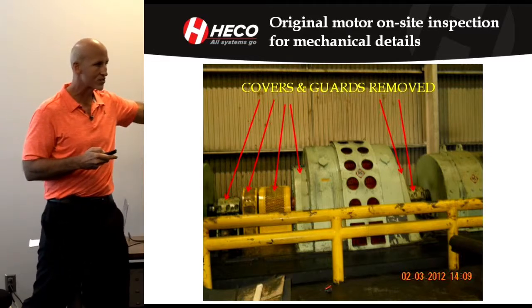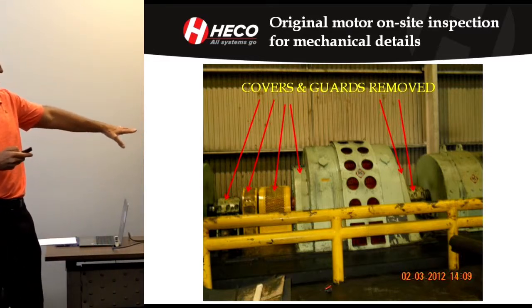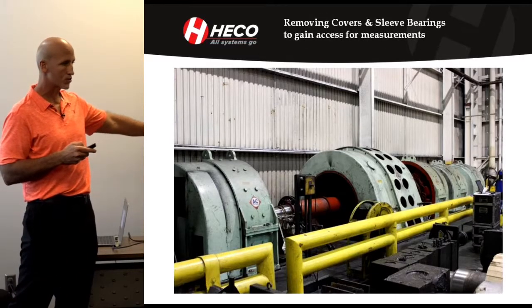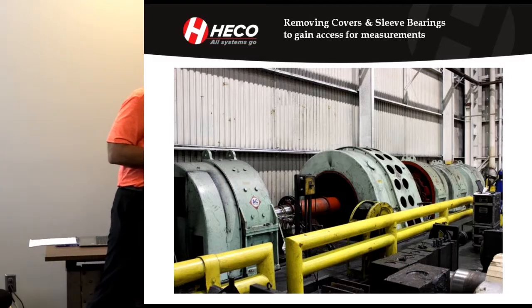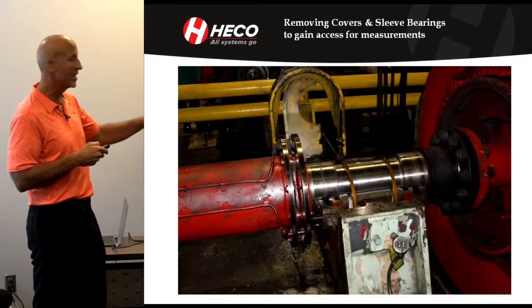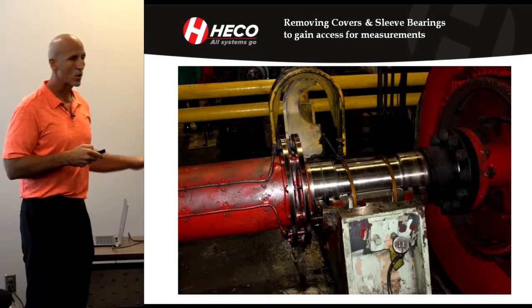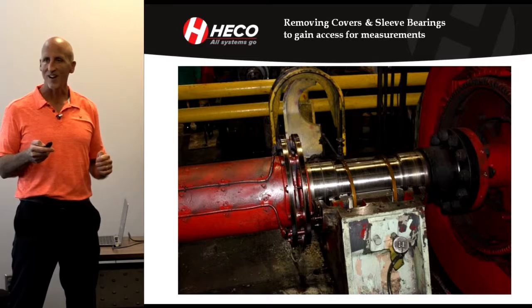Now we had to go on site and get a lot of details. Like back to this motor on site. We were able to have the customer shut it down for a few hours so we could go in and actually, or they pull off the covers and pull off the bearing tops and look at the sleeve bearings and get it to where we could actually physically measure and look at things. But what I quickly realized when we were doing this was that tape measures just aren't going to do it.